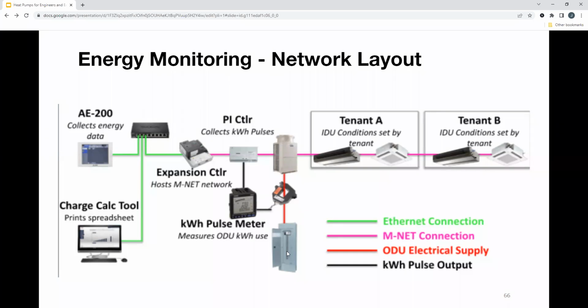And for this, you can actually connect up to 4 outdoor units onto one panel. And to get the most accurate results, we do require that the panel be a revenue grade meter or panel. All right, so this calculates the pulses, and then the pulse output gets tracked by the PI, gets converted into a certain language, and then this central controller over here is basically acting as the energy data storage. One more thing needs to be purchased, which is the software that has the algorithms built in, and it tracks exactly how much energy we're using and which fan coil units are using the most.